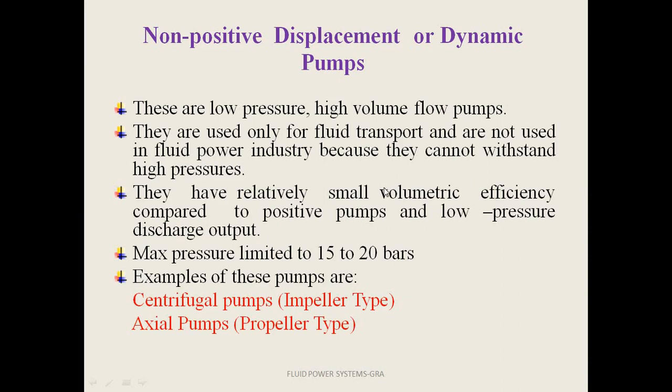Whenever I speak about the term volumetric efficiency in the case of a pump, it should come to your mind that whenever the volumetric efficiency is small, it indicates that the leakage is large. And the other side is also true. Whenever the volumetric efficiency is large, the leakage is very, very small. These are used for a maximum pressure limited to 15 to 20 bars.